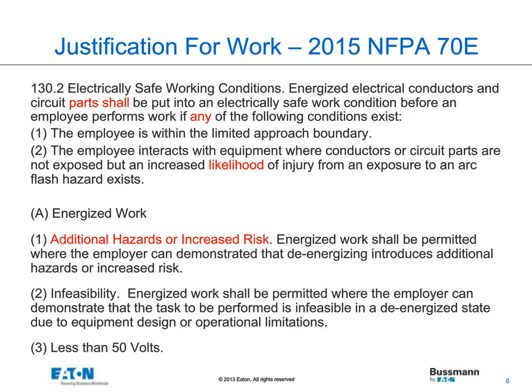With getting into NFPA 70E, what I've highlighted here first is the first article, it's Article 130.2, but it talks about the justification for energized work. Many people think, well, if it's a low risk hazard, I can just go in there and work it. You really first need to justify the reason why you are going in there. And there's really only two good justifications. Either one, there are additional hazards or increased risk, and that used to say greater hazards. And again, the red text shows changes to the 2015 code. So previously it was identified as greater hazard. Now it's additional hazards or increased risk or infeasibility.